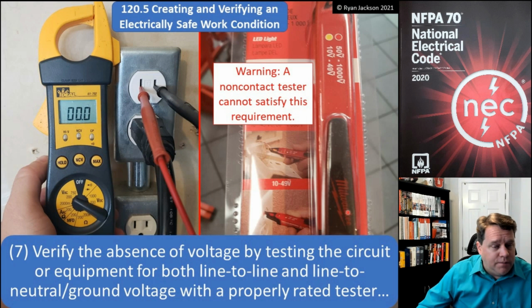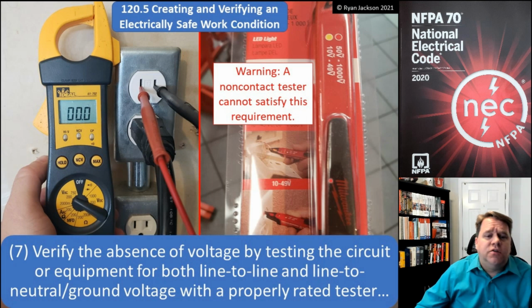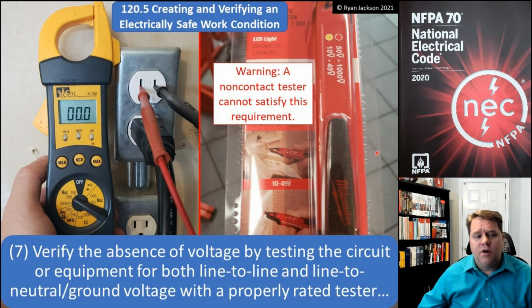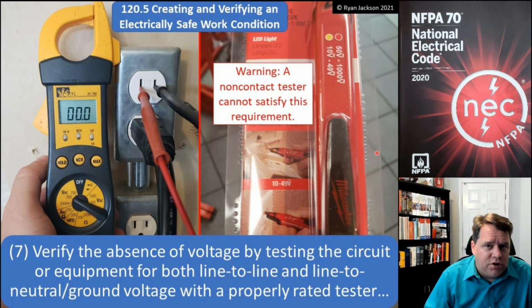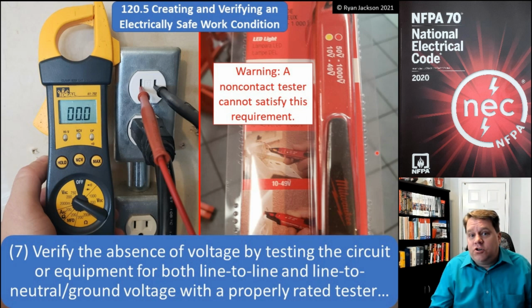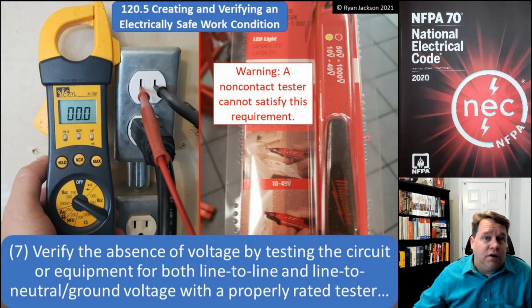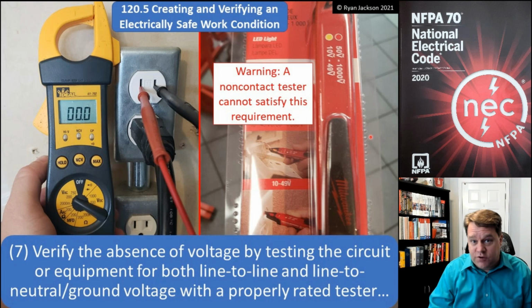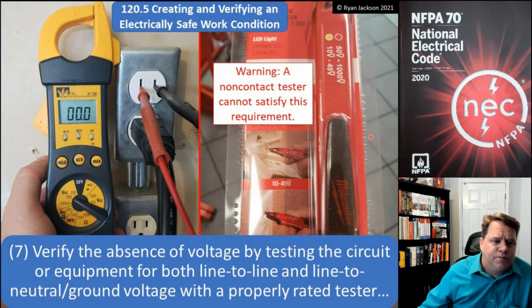And if you think about it, that means I cannot use a non-contact tester like the one that you might carry around in your shirt pocket, because I can't measure line to line and line to neutral with a non-contact tester, at least not up to these voltages, up to 1,000 volts and less. So I need to verify the absence of voltage.